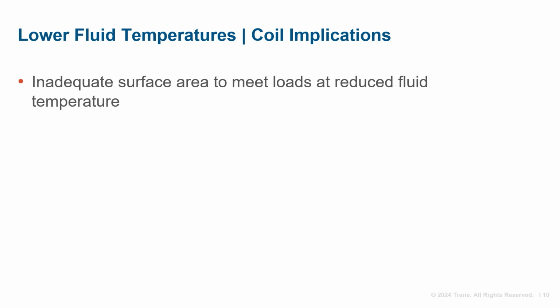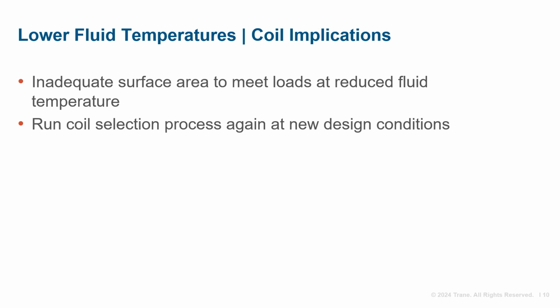We can take the engineering approach. A typical coil selection program can provide data for changing conditions. By modifying fluid temperature into the coil, and for a given flow rate, we can see what happens to the approach on the air side. If pipes can support more flow, we may be able to send more water to the coil to maintain a given supply temperature and volume. If not, there's more work to be done.